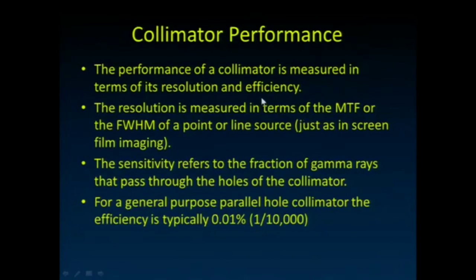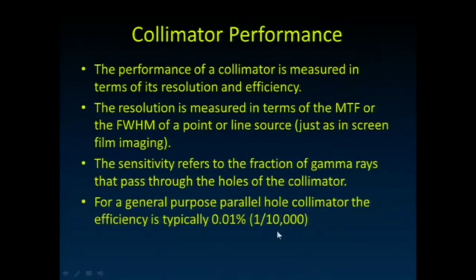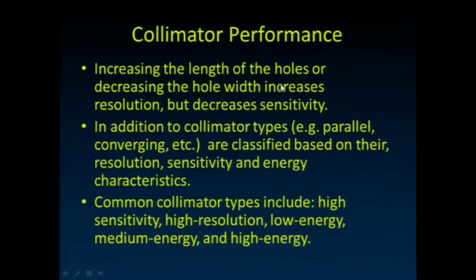Collimator performance is measured in terms of resolution and efficiency. Resolution is measured with bar phantoms, modulation transfer functions, or by imaging a point or line source and measuring the full-width at half-maximum. Sensitivity refers to the fraction of gamma rays that pass through the holes. In most general-purpose collimators, less than one in 10,000 gamma rays exiting the patient actually makes it through the collimator holes — a similar inefficiency to x-ray imaging. Increasing the hole length improves resolution but worsens sensitivity, just as with the grid.